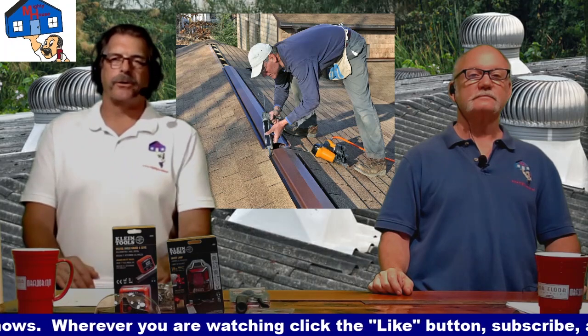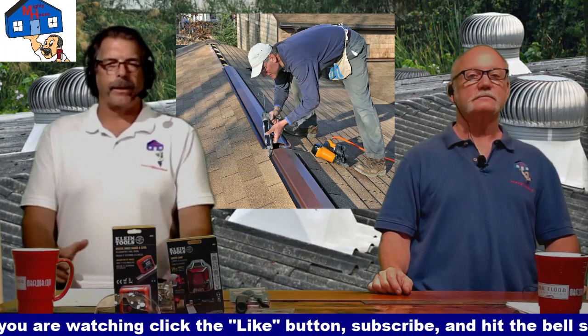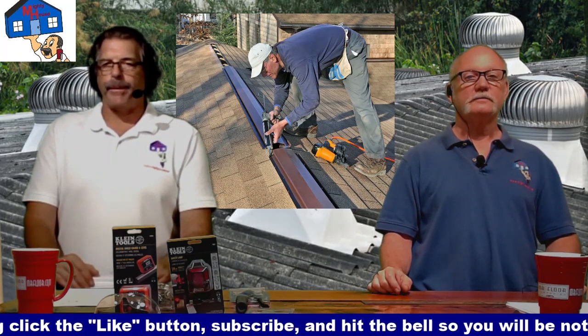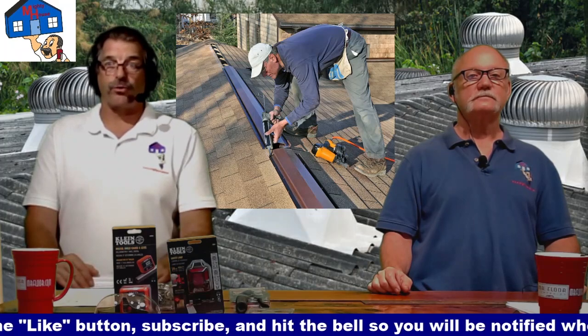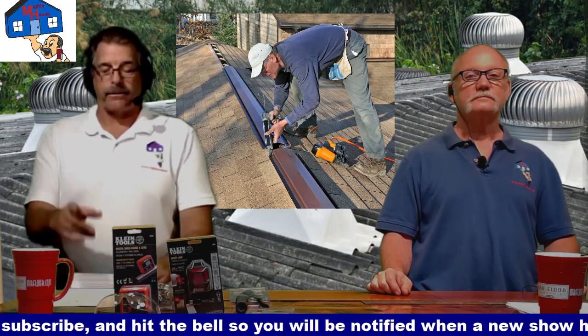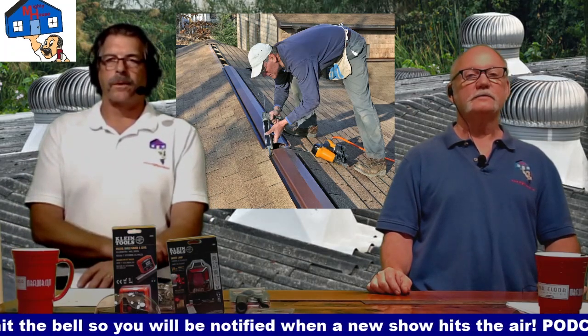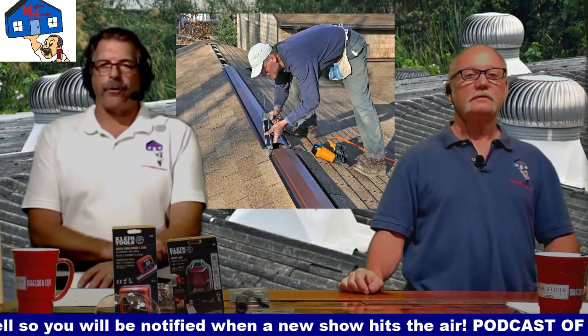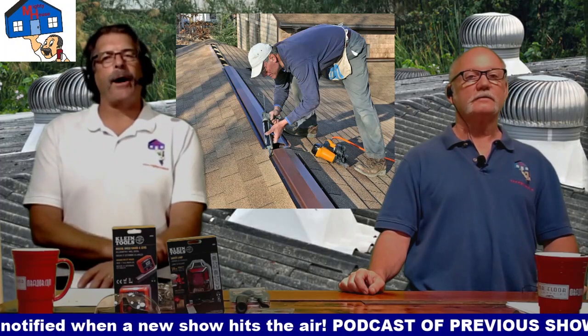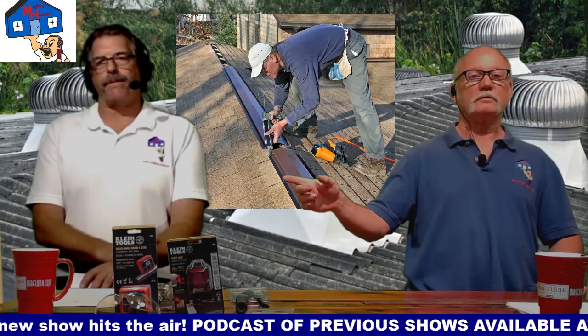Now, I never saw those when I worked in Chicago. But it's almost all we use on shingle roofs down here in Florida. Okay. And I'll be honest, it's what I have on my house right now. Let me give you a number on that: 21 square inches per foot. Okay. So for every 2 feet, I can equal a mushroom vent. Yeah. So now we're getting more doable here. That's a technical term, doable.